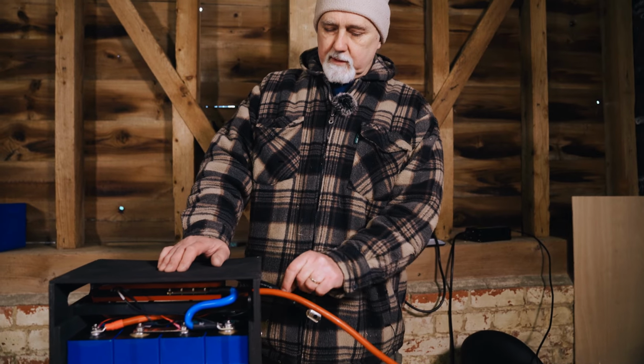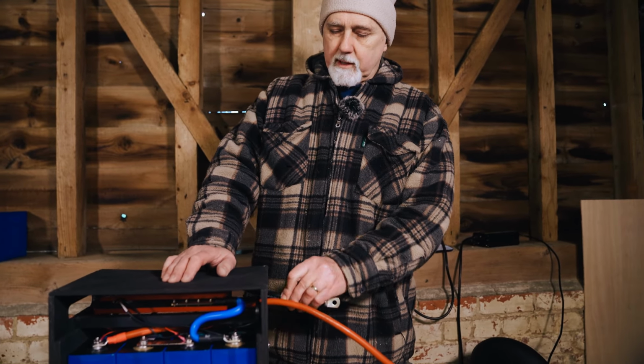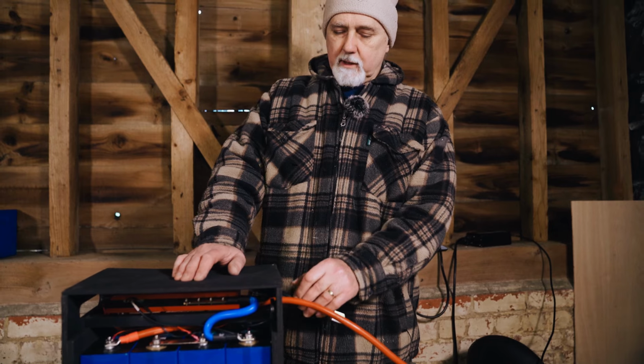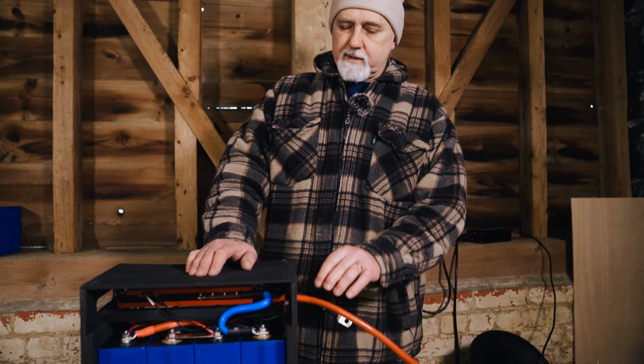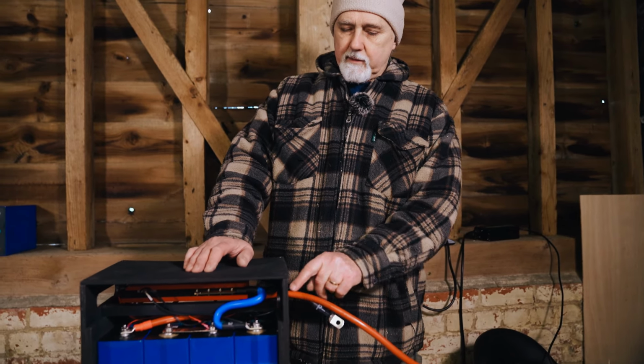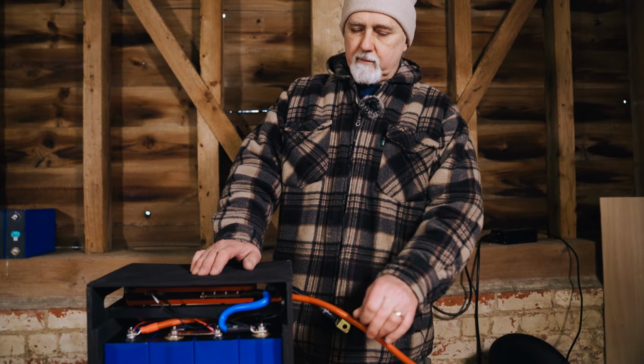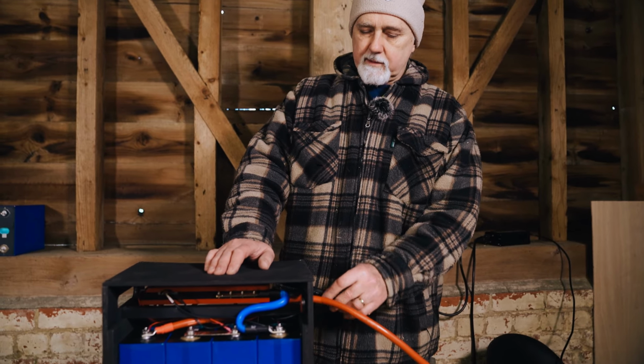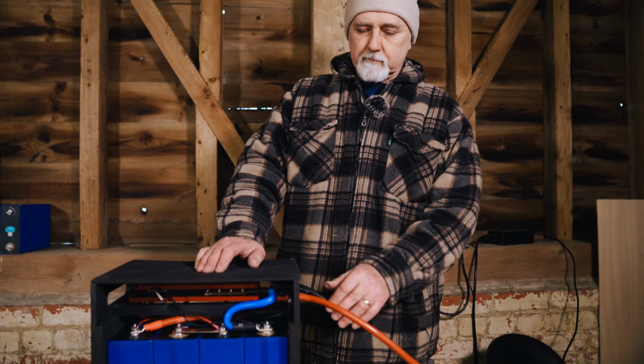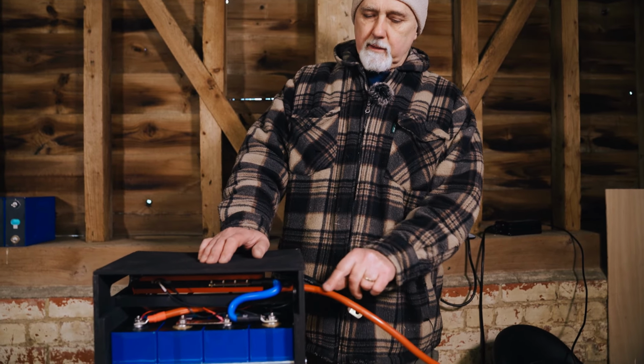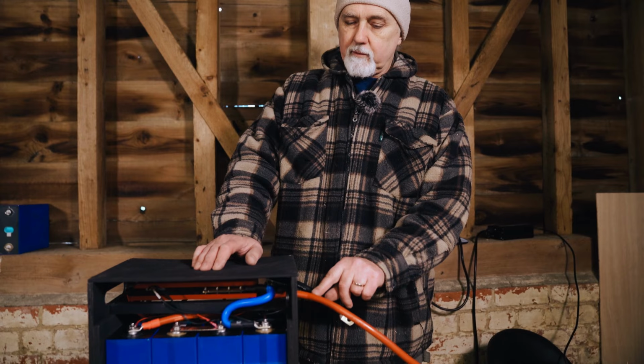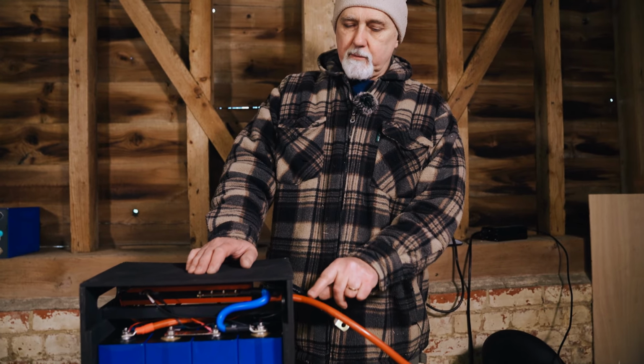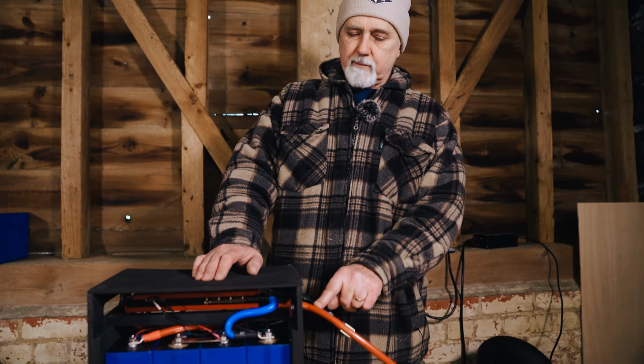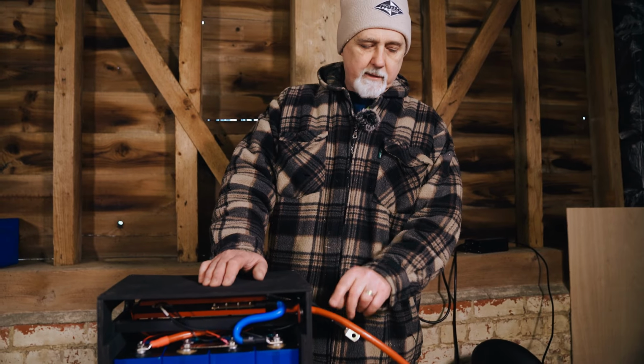So this is a 2 American wire gauge, AWG cable, this is a 35 millimeter, which is the same as this. This one is rated, I think, at about 105 degrees centigrade. This one is rated at 200 degrees centigrade. You can buy the more expensive 2 AWG or 35 millimeter cable if you want, rated at 200 degrees centigrade.